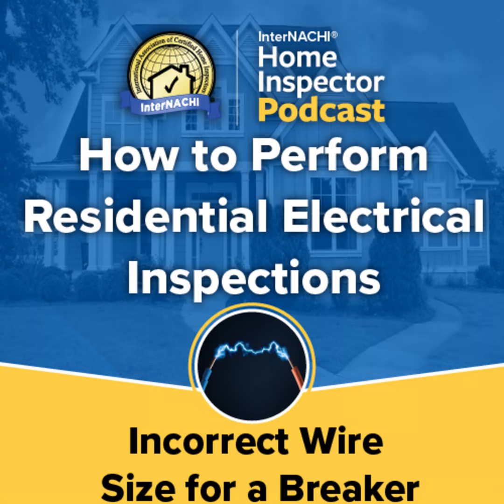If the bare wire end is visible, a home inspector may be able to observe and determine the wire gauge, but just seeing only the insulated wire can make identification more difficult. A home inspector should never insert a potentially conductive instrument into the electrical panel in order to take a measurement of the wire gauge. If an inspector uses a wire gauge measurement device, it must be tested and confirmed to be non-conductive. Different manufacturers have different thicknesses of the plasticized insulation on the wire, which may make an inspector look for other clues to the wire gauge, particularly the labeling on the wire itself.